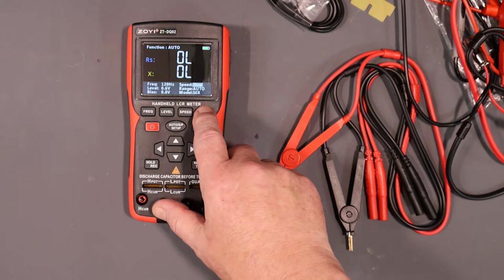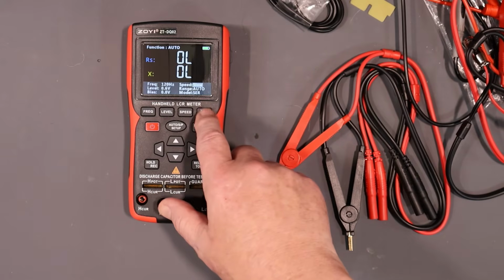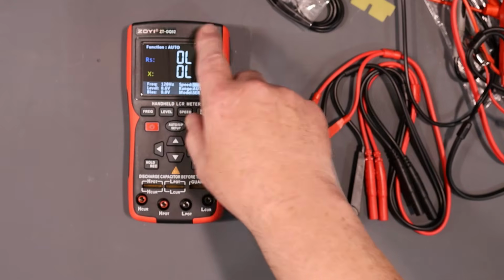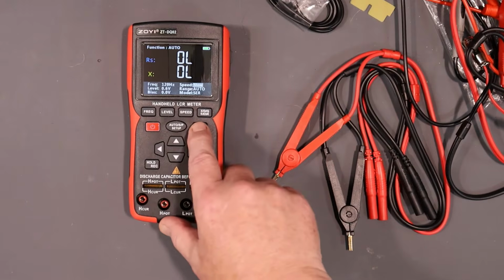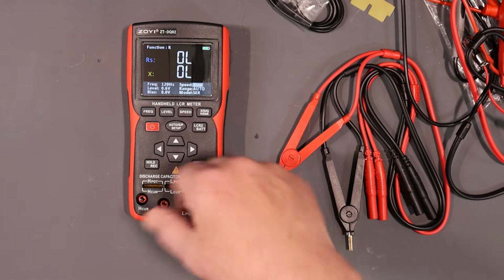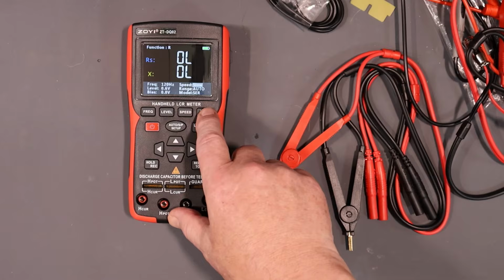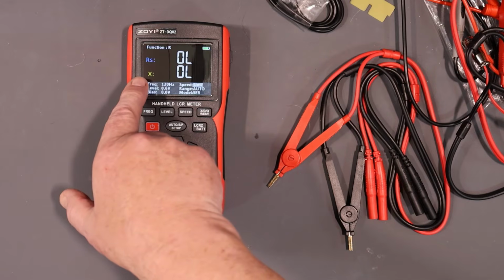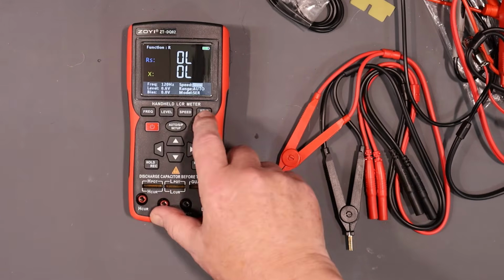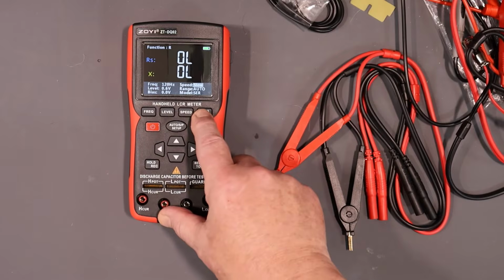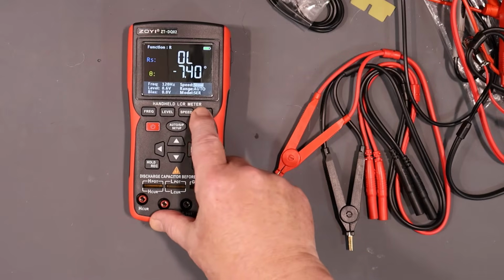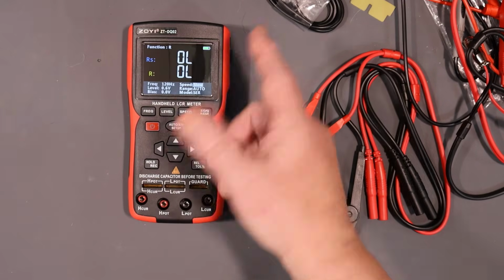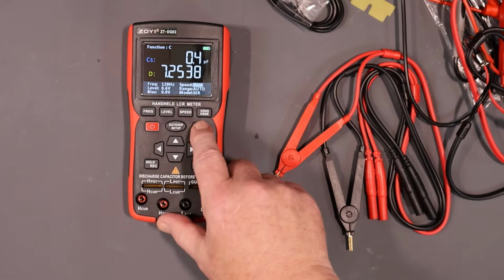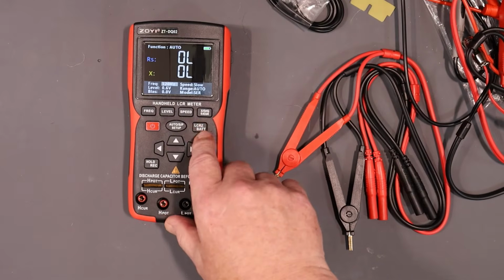This button here selects the secondary test you're doing. So right now we're in auto, so let's go over here. We'll go into resistance, for instance. And what you can do here is, right now we're testing for reactance, and you can change that. You can test for phase angle. You can check for series resistance, dissipation factor, and quality factor. This is kind of your mode.